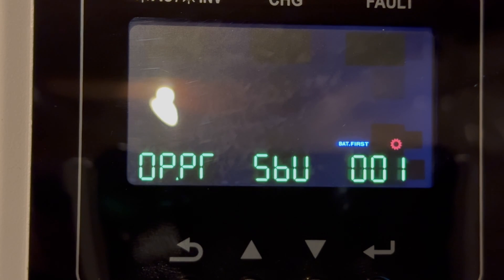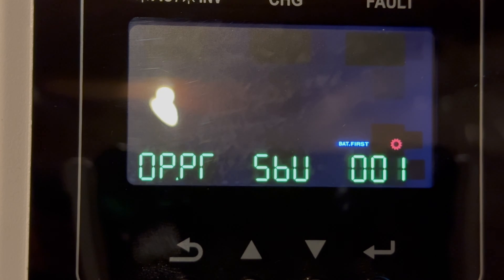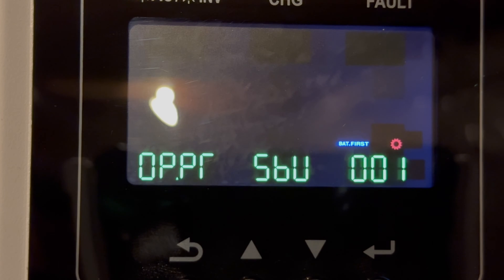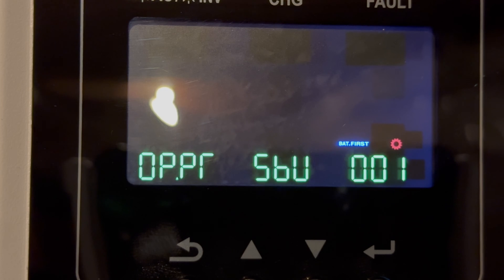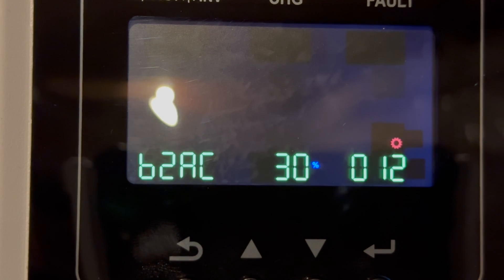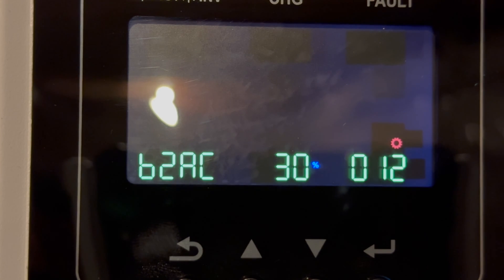In this first setting, it's the SBU mode — Solar Battery Utility. Solar Battery Utility means it uses solar and battery, and if those are insufficient, it will switch to the utility. This is our common run mode so that we can utilize the sun and the battery and only use the utility in the event that we actually need it.